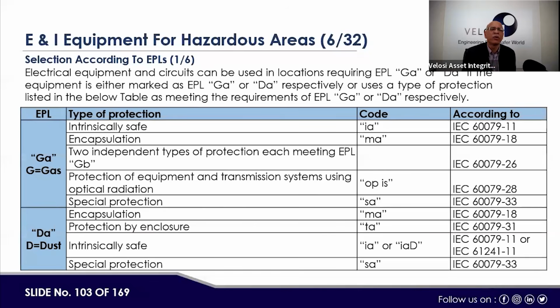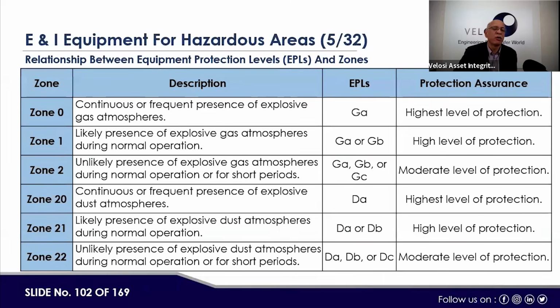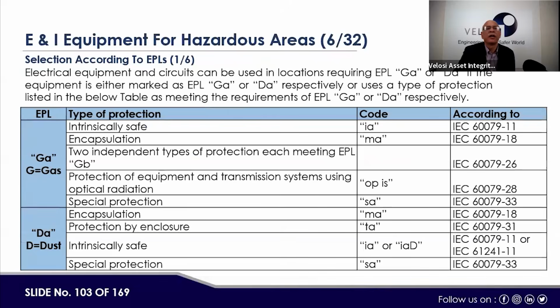That will depend upon what kind of zone district the equipment is installed in. Like I've gone to the previous slide, whether zone 0, zone 1, or 2, and accordingly the EPL class is required. For dust, DA class is also required. For gas, GB or GC class is required. So this defines what kind of protection is required for the equipment: the EPL class, right?